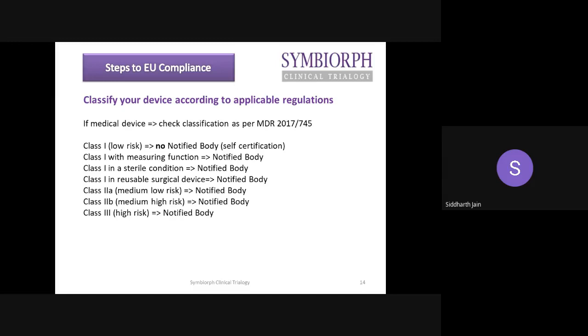If it's a class 1 with a measuring function, we call it a class 1M medical device. Then further, there is class 1S medical device, which means class 1 sterile. And there's also a classification for class 1R. 1R means reusable surgical device. So all the devices which require any type of reusability, you can classify into class 1R.